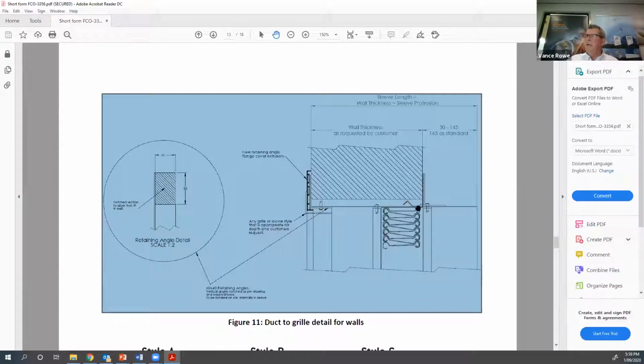You can see the damper there, our locating springs, because we don't wrap our fire dampers with any sort of barrier anymore. That's the intumescent seal. And then there's the mounting angle on the right-hand side there where I've got the arrow, and you can see the duct going off that way. There would be a requirement to put a duct on that. Although, I'll just stop sharing that for a minute, I have actually helped people in the past to put a wire cage over the back, and through a lot of the testing that I've done, there's good evidence to assume that we lose heat very, very quickly from the fire damper.